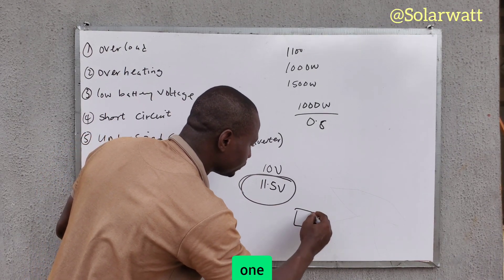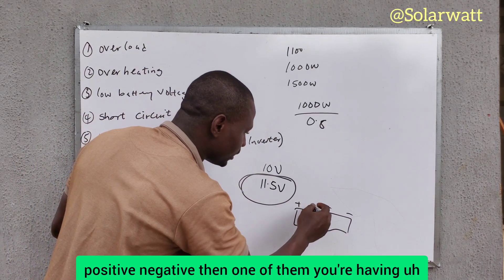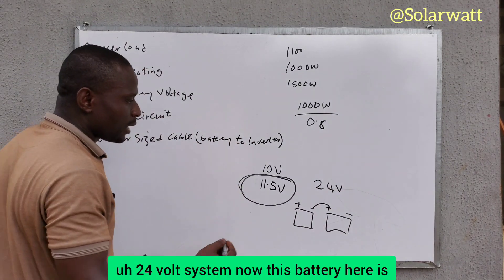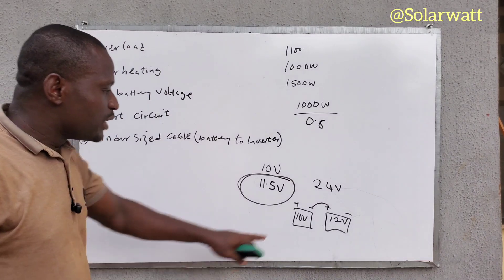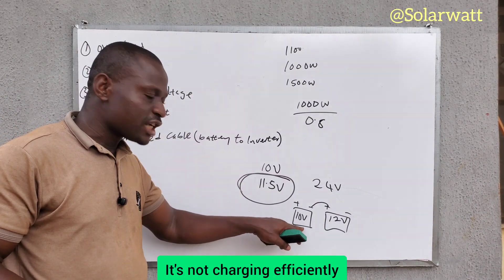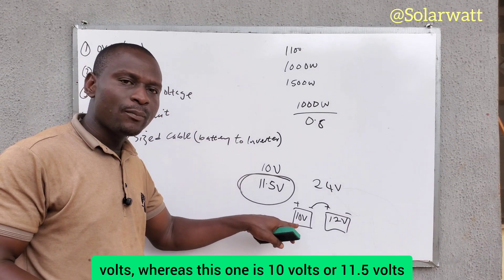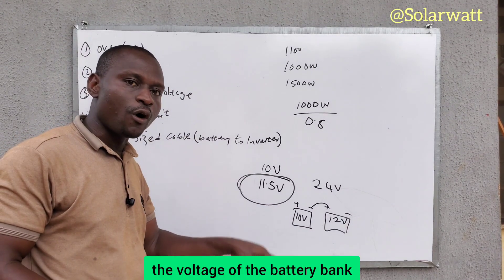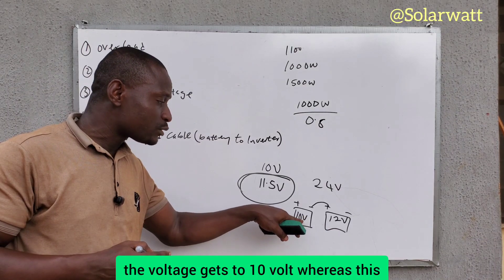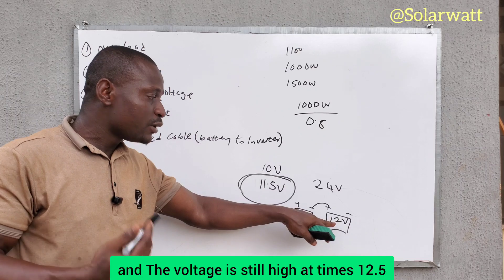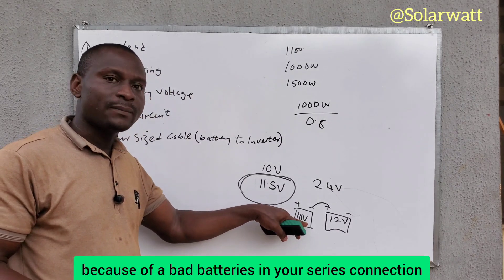For example, in a 24-volt system with two batteries in series, if one battery reads 12 volts while the other reads only 10 volts, the low battery is bad or undercharged and not charging efficiently. One battery may be at 12.7 volts while the other is at 10 or 11.5 volts. That bad battery will drag down the voltage of the entire battery bank, so the inverter senses the low voltage of the bad battery. Once its voltage drops to 10 volts, the inverter will shut down even though the good battery's voltage is still high.